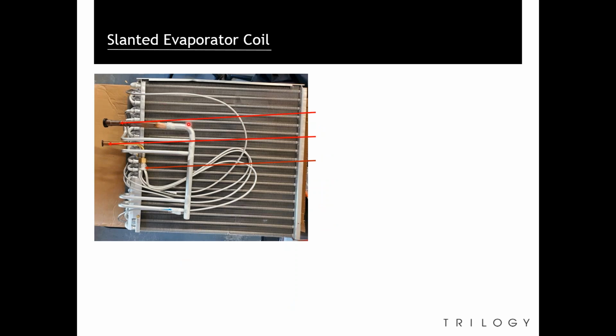This is a slanted evaporator coil. This is the low side port. This is the high side port. This is the orifice with a piston. We will be charging this with superheat.